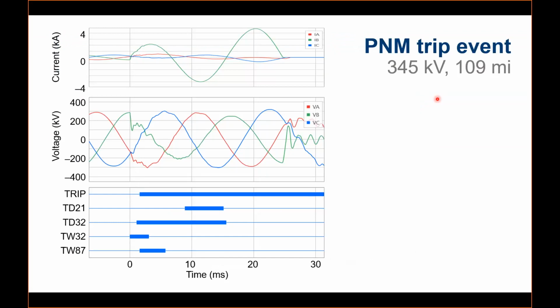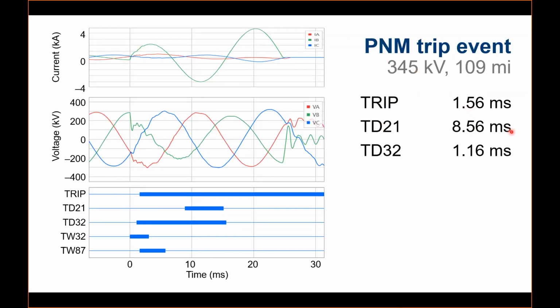There are a few real-time events that we recorded on the lines. There's one line of the utility PNM in Mexico. It's a 345 kV line, and we have captured some current and voltage waveforms, and this is the response of the elements. The trip happened in 1.56 milliseconds. You can compare this with the conventional technologies, taking 1 cycle or 1.5 cycles to decide and trip. The distance element responded a little bit late. Direction elements are faster, and TW87 is basically causing the trip. So that's 1.56 milliseconds, and it's a 109 miles or about 170 kilometers line.